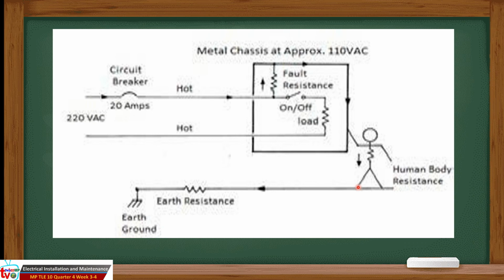In addition, the earth resistance may or may not be less than 6 ohms. The only requirement in the Philippine Electrical Code is that the resistance of the grounding electrode ground rod be less than 25 ohms. Hence, even if the appliance is not isolated from earth ground, the ground resistance may limit the fault current to below the trip point of the circuit breaker. Furthermore, there is usually considerable resistance between the appliance and earth ground. For example, the appliance may be sitting on a concrete slab.